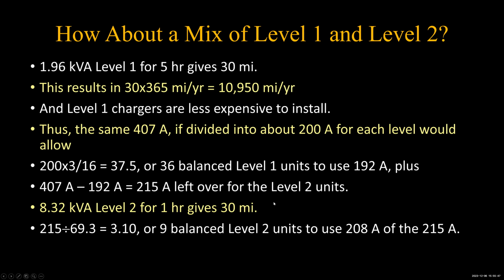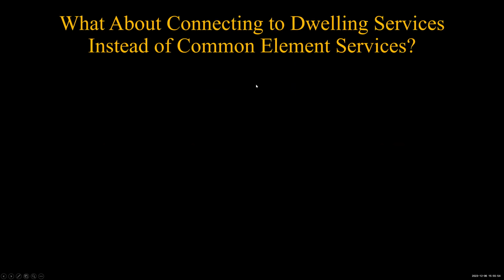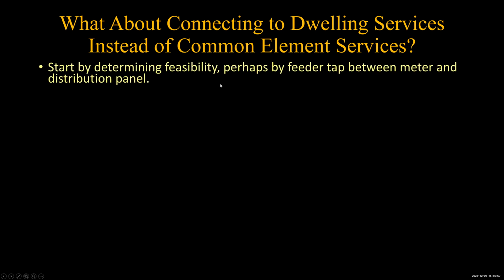So we've already shown how we can take care of all the vehicles there. But if we get outside of, if you just try to connect to dwelling services, there can be a problem on that, and that's because of the derating factors. If you do the regular calculation for 1 unit and then you got 25 units, you're going to have a derating down to about 30%. And it's that total load on the distribution system of meters. If you got a 25 meter bank, it's the total load on those 25 meters that you have to add your one additional charger to. And it's very easy to go over by connecting them to the individual dwelling services.